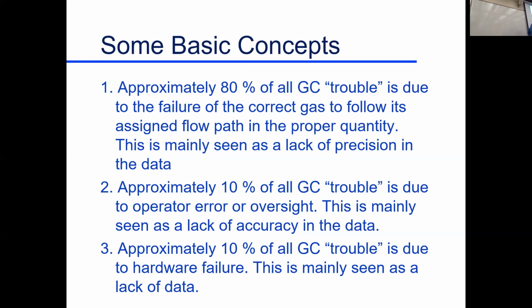Approximately 10% is due to operator error. You screwed up, okay? 10% is actually due to hardware, so something went wrong with the instrument. And I'd probably bring that number down to 1% rather than 10. We have almost no problems with the hardware. Most of the time, it's something we've done, or like I say, something in the plumbing.